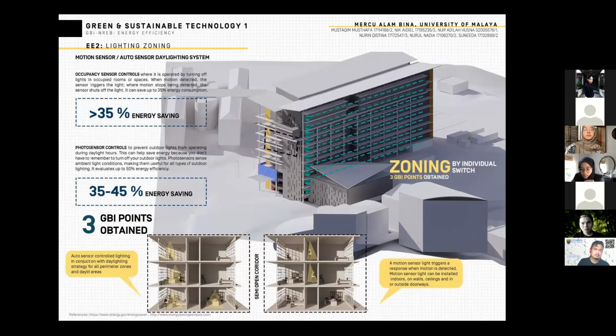As you can see here, the green one is the system where occupancy sensor controls would like to be installed, which can save up to 35% energy from consumption. The new proposal we'd like to propose is photo sensor controls, which can prevent outdoor lighting from operating during daylight hours. It can save 35 to 45% energy according to our reference, so the total GBI points obtained is 3.